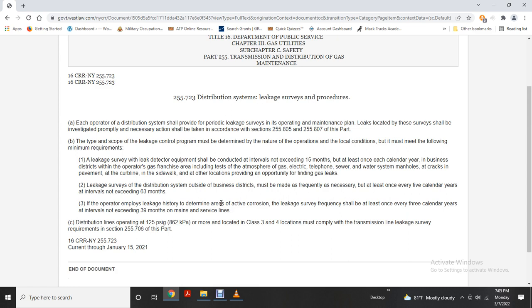The leakage survey with leak detector equipment is conducted at intervals not exceeding 15 months, but at least once each calendar year, in business districts within the gas franchise areas, including testing the atmosphere of gas, electrical, telephone, sewer, and water system manholes, cracks in pavement, curb lines, sidewalks, and other locations that provide opportunity for finding gas leaks. A leakage survey of the distribution system outside of the business district must be conducted as frequently as necessary, but at least once every 5 calendar years, at an interval not exceeding 63 months.